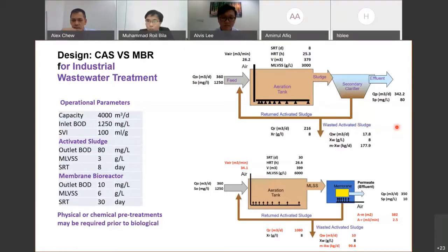Now you can see from this calculation, for activated sludge, if you have a feed of 360, we will have to waste about 18 cubic meters per day. That is less than 5% of the volume going to form the excess sludge.